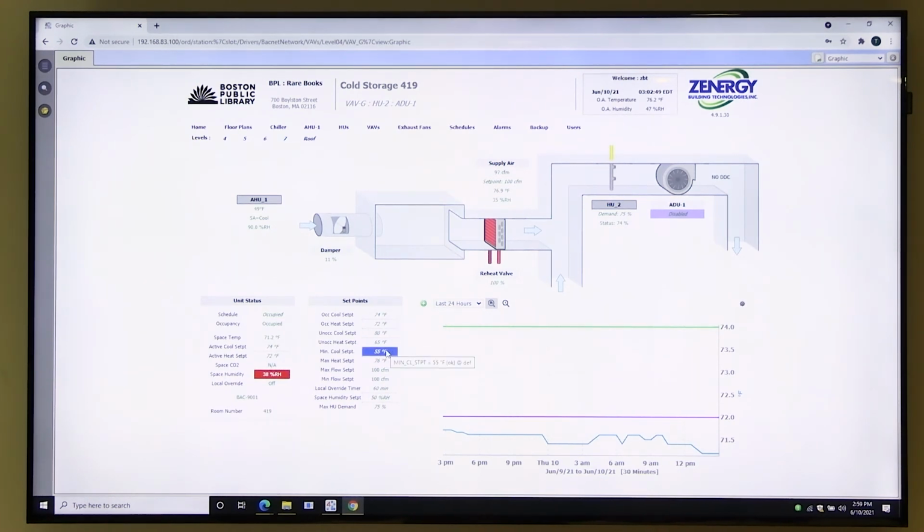That's really not going to have any effect, honestly, as far as what you're looking at here. You really care about the heating set point, which sounds like you never really want to be heating in this space. This VAV damper, because it's constant volume, is just air being dumped in from that air handler, but it's never actively cooling the space.